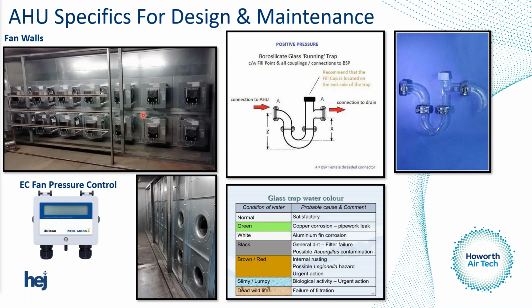And the benefit of these is we can sort of reduce the risk. There's a redundancy risk argument that could be had. So if one fan comes out or fails, the other fan must achieve 80% of the flow rate through the air handling unit. We get better heat transfer with these type of fan walls, better movement of air down the air handling unit. So these are a really good thing. I think they're going to become quite popular, I believe.